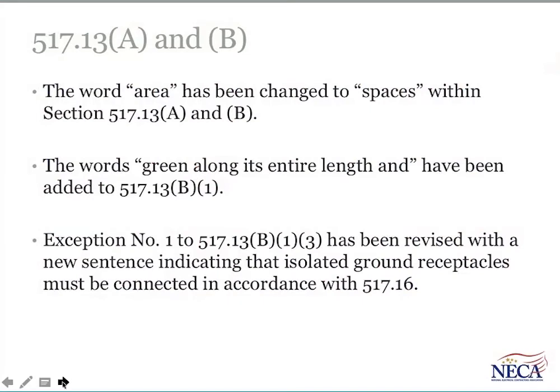Section 517.13(A) and (B), that's in Part 2 of Article 517, dealing with wiring and protection. The change extends into this section and other sections throughout Article 517 to change the word area to space. And within this section that requires the two grounding paths for branch circuits serving patient care spaces, there's a clarification about the wire type equipment grounding conductor within those metallic raceways. The words green along the entire length of the conductor have been added for clarification. There's also an exception there that talks about isolated grounding type receptacles, and that exception was revised to point to Section 517.16.